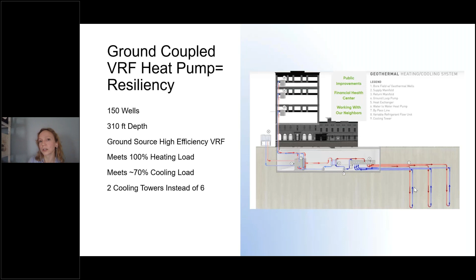The ground coupled VRF, heat recovery VRF systems were another key part of this all-electric project. There are 150 wells, quite deep, designed to meet 100% of the heating load. There's no auxiliary heat on the building, no electric resistance, and I've got an example that shows the capacity of those wells is enough even in very extreme conditions. It meets about 70% of the cooling load, and there are 2 cooling towers, reduced from 6. So we've got 400 tons of peak load cooling capacity, an 800-ton reduction from what the design was originally.